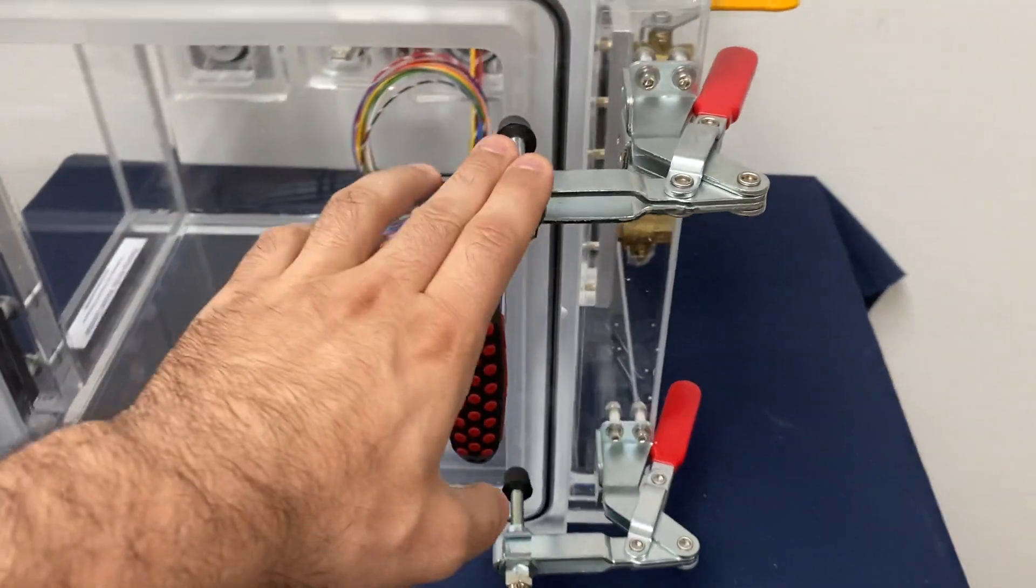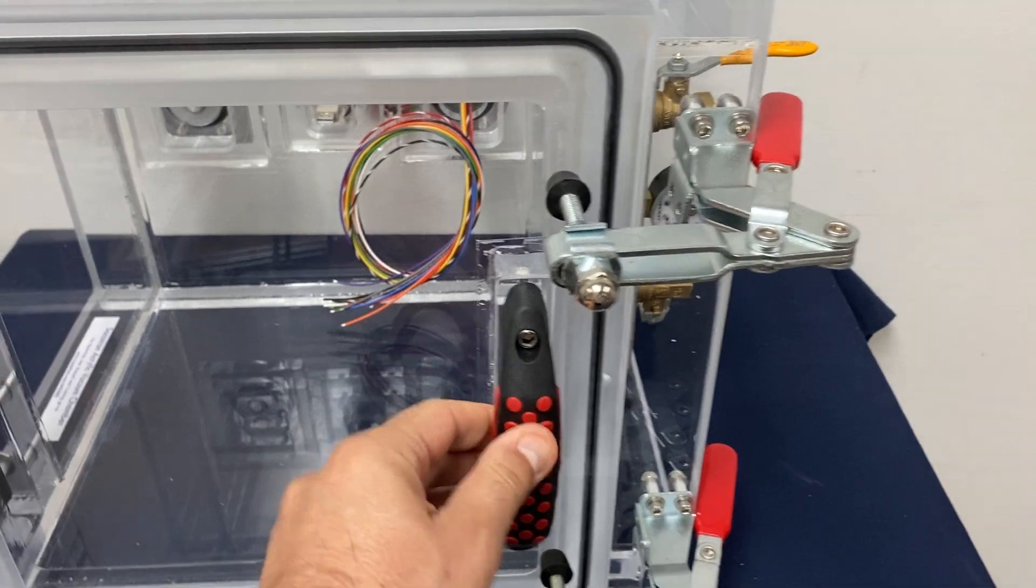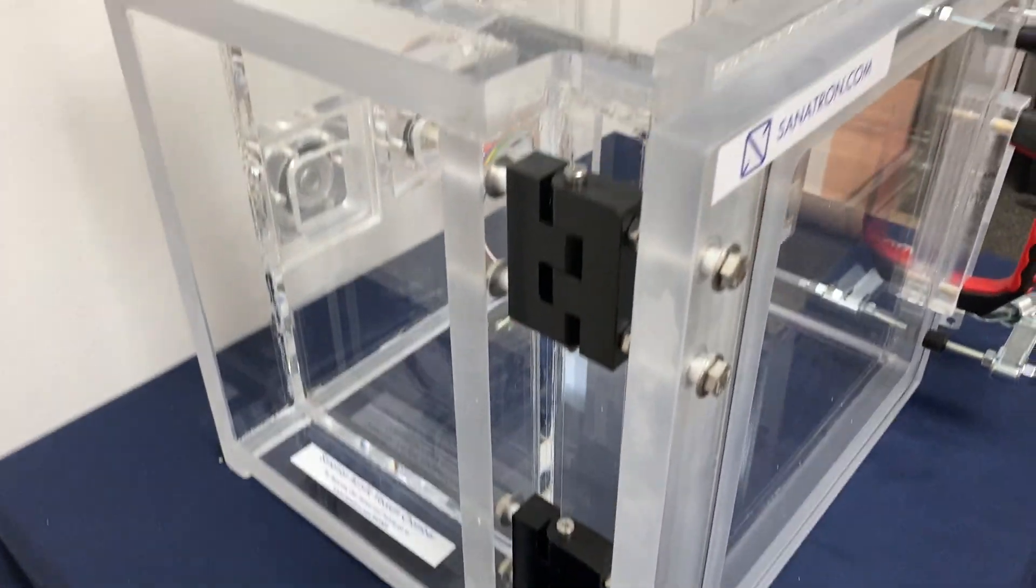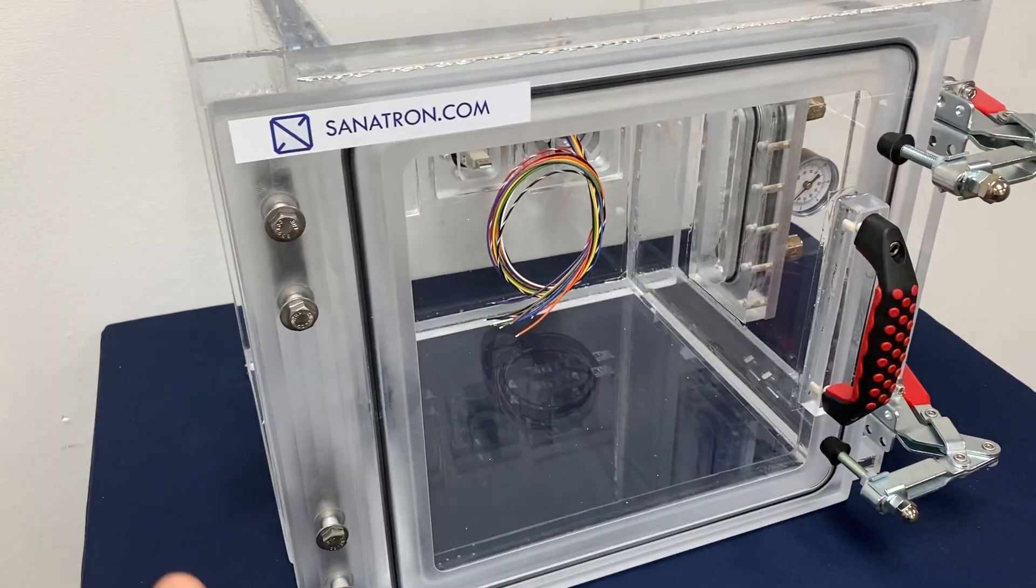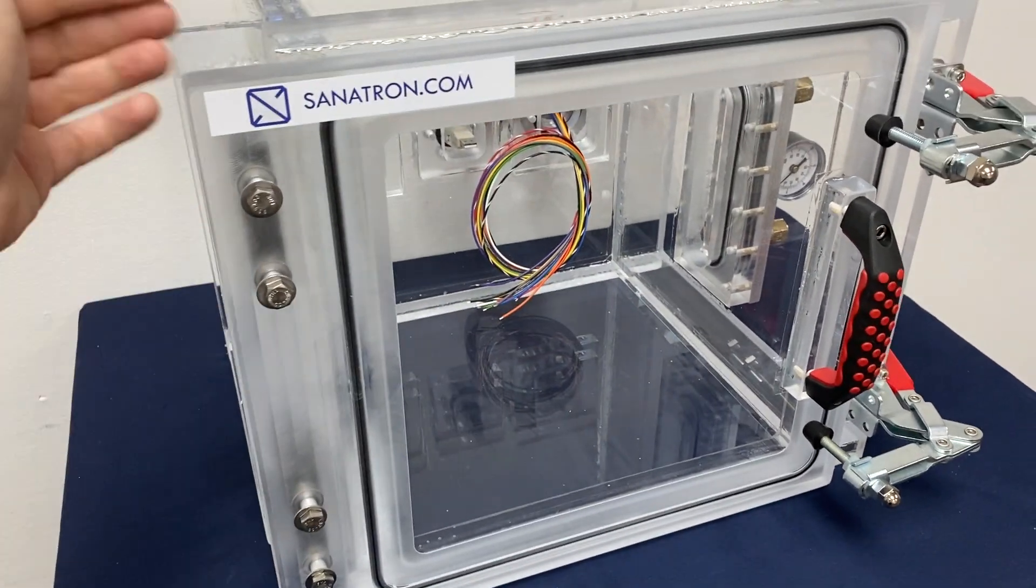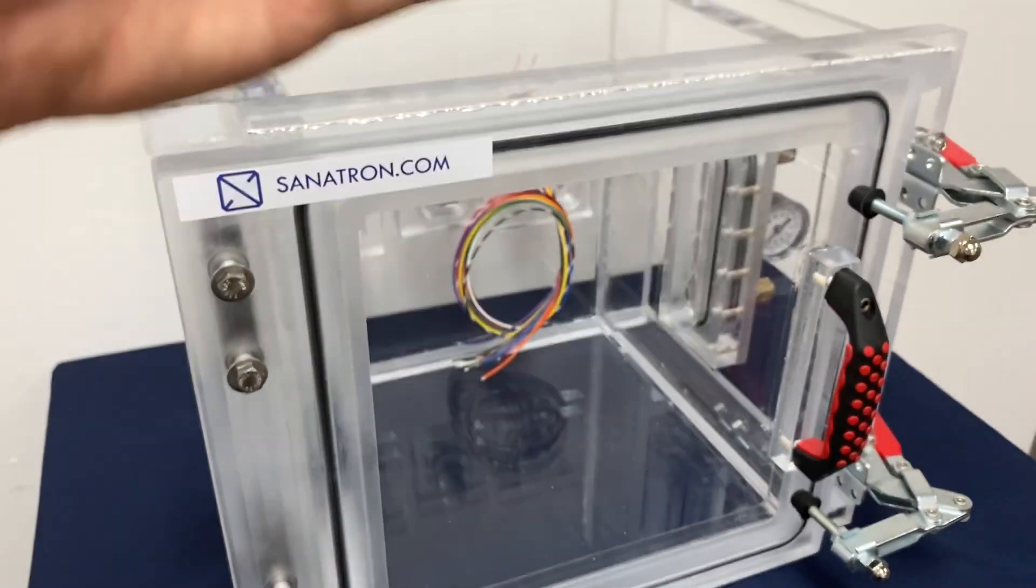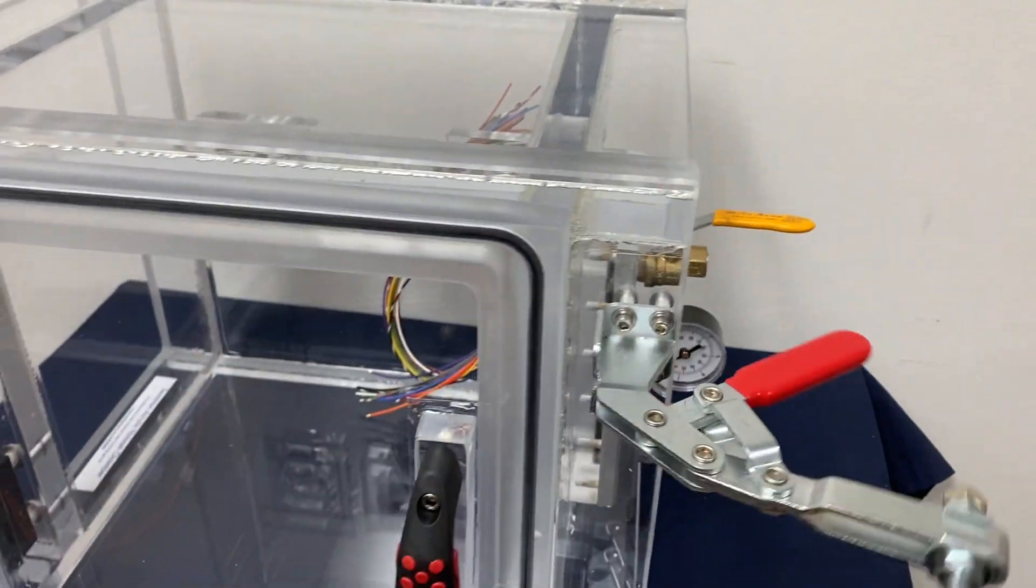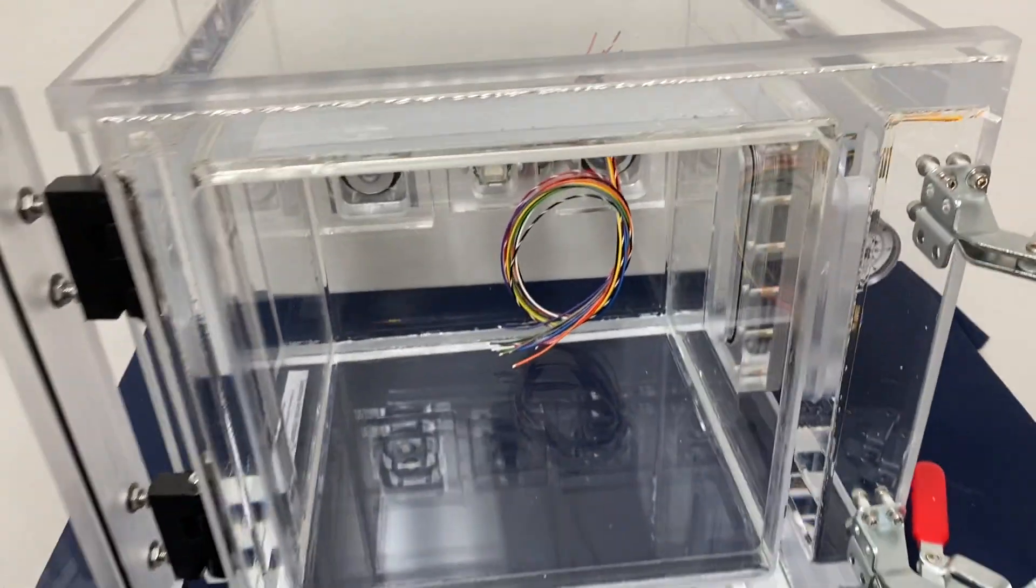This door comes with two clamps, one lid handle or door handle, and also two adjustable hinges so that you can adjust your door in case you ever need to replace your O-ring. You can replace the O-ring and then adjust your door to make sure that it is fully sealed and also fully parallel to this wall so that you can get a good seal. Alright, let's open these clamps and let me show you inside this chamber.